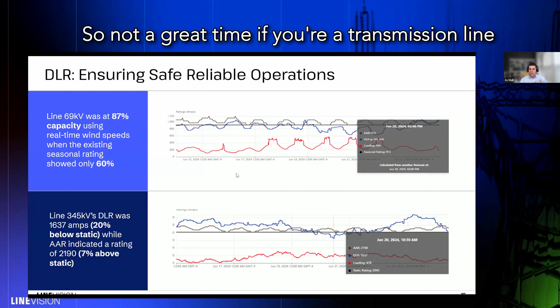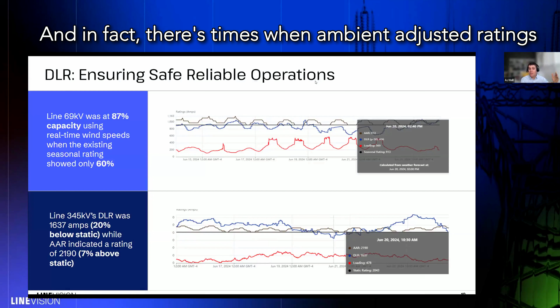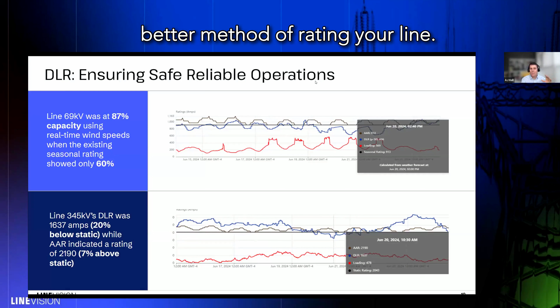You can see that the blue line in both graphs actually dips below both the ambient adjusted rating and the static rating. And in fact, there are times when ambient adjusted ratings are telling us we have more capacity on the line, but DLR is telling us we have less. And why is that? It's because DLR is a much better method of rating your line.